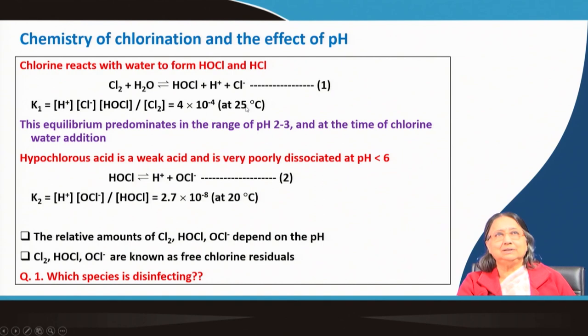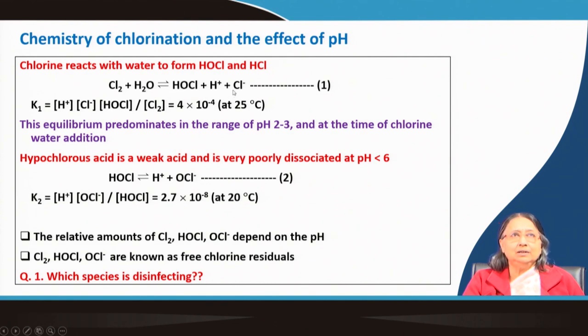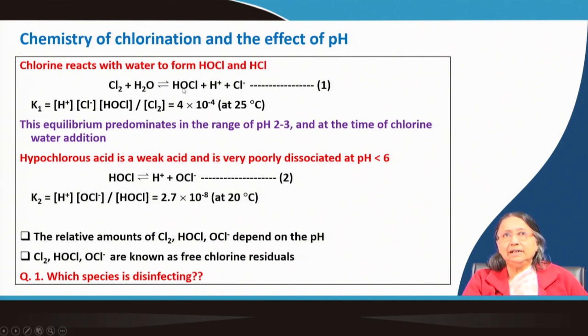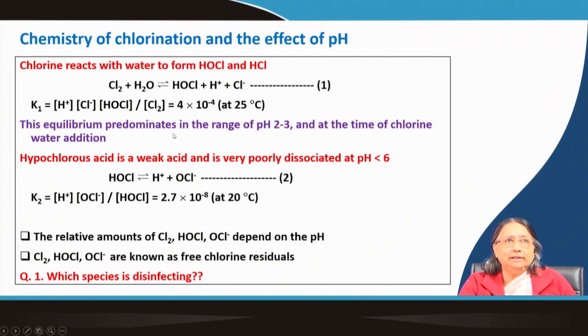This equilibrium predominates in the pH range of 2 to 3 at the time of chlorine-water addition — pH goes down because H⁺ is produced. If you increase the pH, more and more HOCl will be formed and chlorine concentration will reduce. HOCl is a weak acid, always in equilibrium with H⁺ and OCl⁻. The equilibrium constant for HOCl ⇌ H⁺ + OCl⁻ is K₂ = [H⁺][OCl⁻] / [HOCl] = 2.7×10⁻⁸ at 20°C.